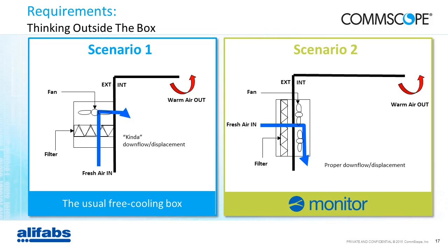Because both solutions in both those scenarios are using centrifugal fans, the airflow has got to be perpendicular. And in our system, to allow it to be more compact, we have designed it in such a way that it provides a proper downflow air displacement because it blows towards the floor, and it doesn't need any sort of direction grill to do that. So that was one of the first simple differentiators that we added to our solution.